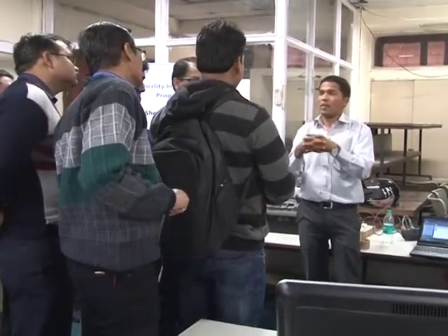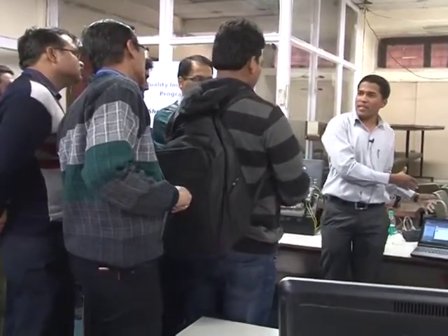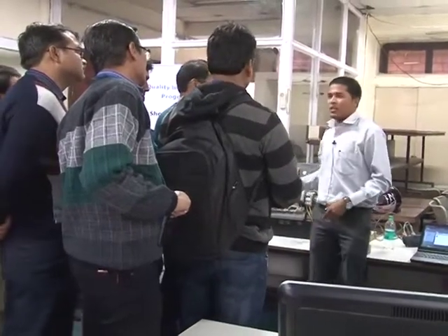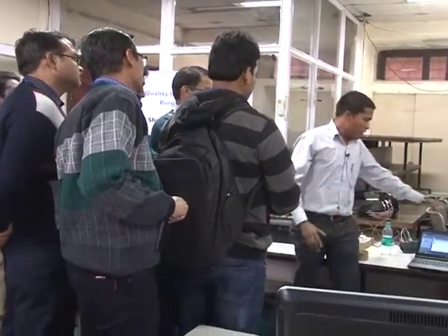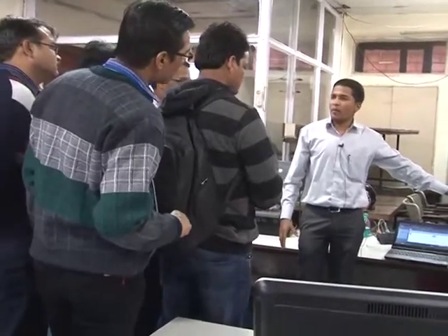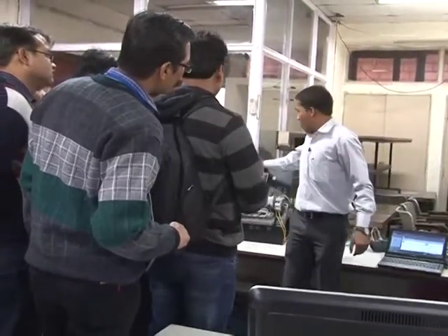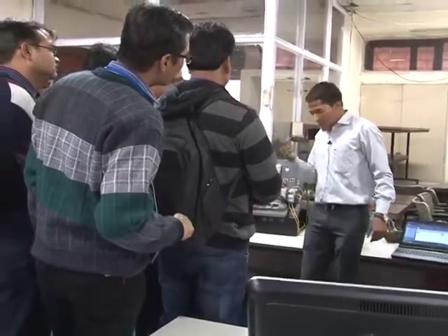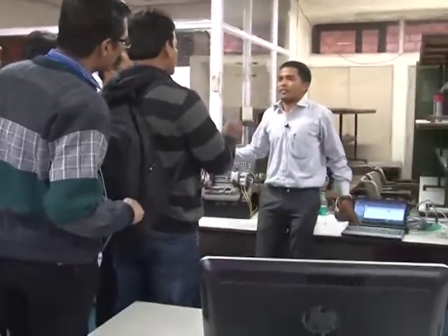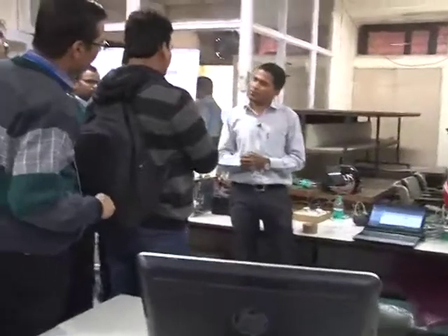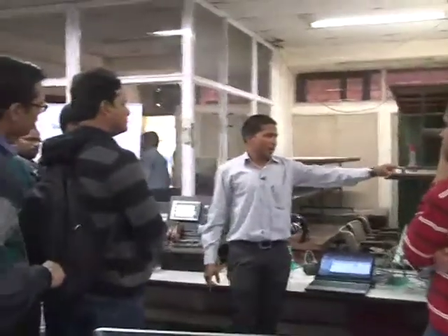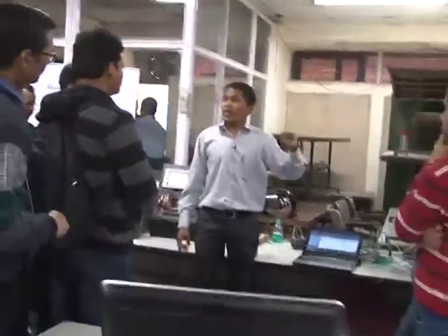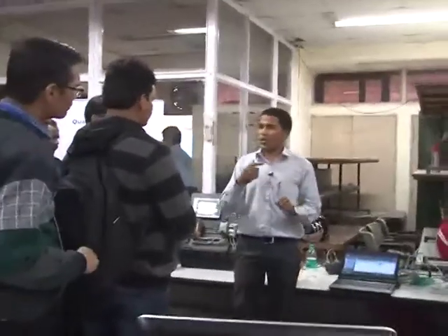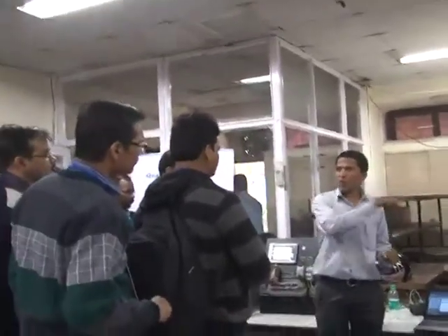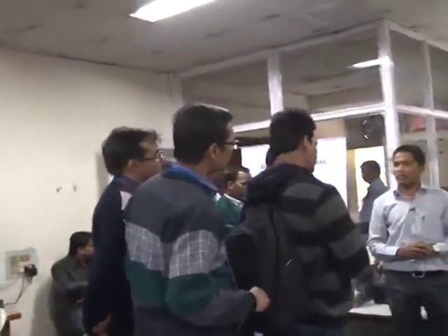But both understand one common language - which language? Modbus TCP/IP. So my PLC understands the same language and this PLC also understands the same language. So what I made here is a Modbus TCP/IP server and a Modbus TCP/IP client, and with this common protocol I am sending the data. Only due to this Modbus TCP/IP? Yes, both are getting it. But in this case, this sensor understands the Profinet signal, Profinet protocol, and my PLC understands the same, so I can directly give the signal through that Profinet protocol, and you can configure that here.